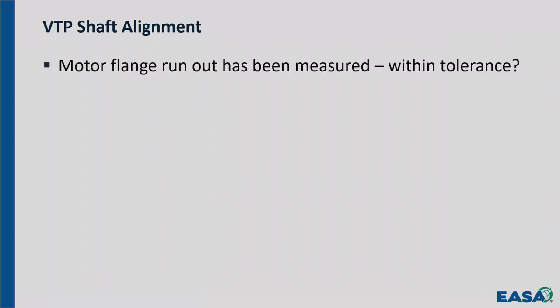Okay? Shaft alignment is a problem. The motor flange, you know it's true. You check that. No problem. You don't know what the pump flange is that's mating. It could be eccentric. It could be out of square. There's no way to test it. There's no easy answer to this.